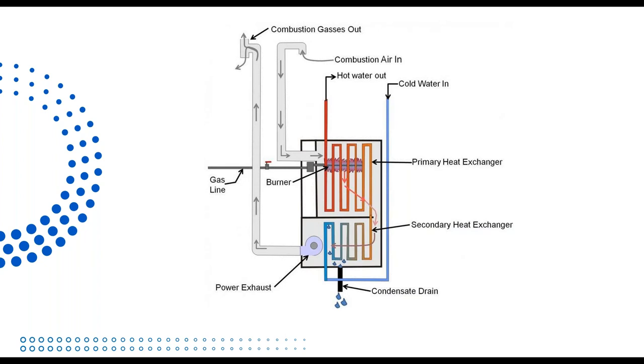So this is our number one competition. It's a condensing boiler, natural gas. Just a recap of how it works: you need a cold water temperature return in order to condense the flue gas. The flue gas dew point is typically 140 Fahrenheit. So if you're coming back at 160 Fahrenheit here, it will never condense. So we see more and more designs with a set point around 120 Fahrenheit with a return around 90 Fahrenheit to make sure that all year round it will be under 140 Fahrenheit return, right?